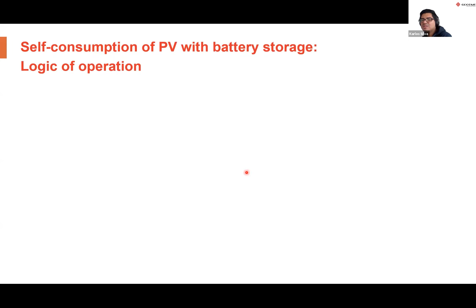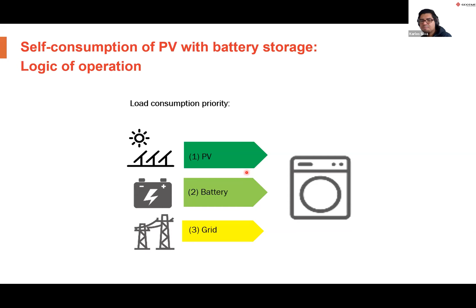Looking at the logic from the load side: imagine yourself as a household load or appliance. You'll draw power first from the PV array. If there's not enough power from the PV array, you'll draw from the battery. And if there's not enough instantaneous power from the battery, or if it's at a low state of charge, you'll then draw the balance from the grid.